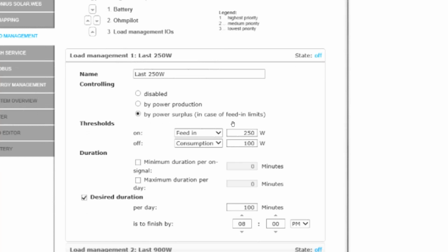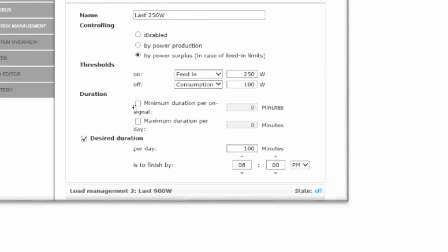And then we have to set, very importantly also, what is the minimum duration per on signal, so that this would prevent too many on and off cycles of that particular load. So that if it's a pool pump or something like that, you might want to say that whenever I put on the pool pump, I want to run for minimum 5 minutes, regardless whether there is excess energy available or not, and then switch it off within 5 minutes if I'm consuming a certain amount from the grid.